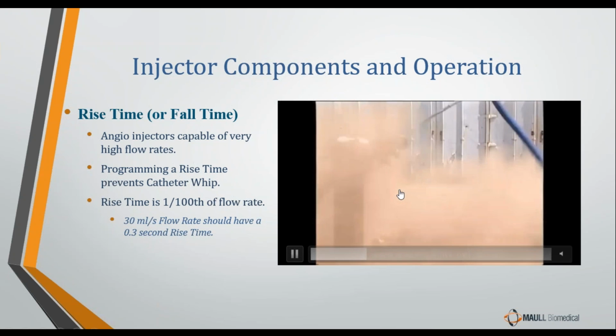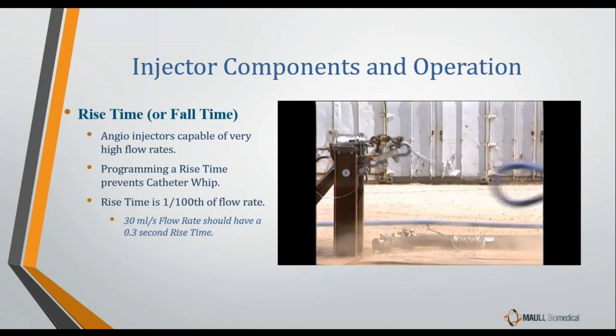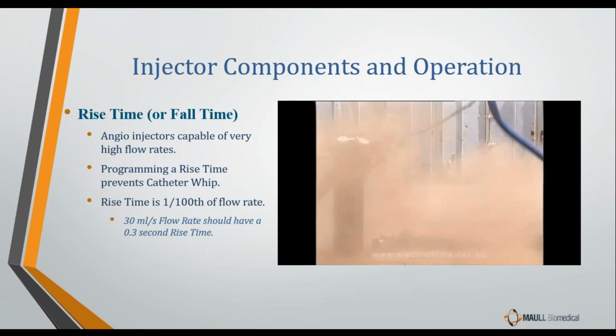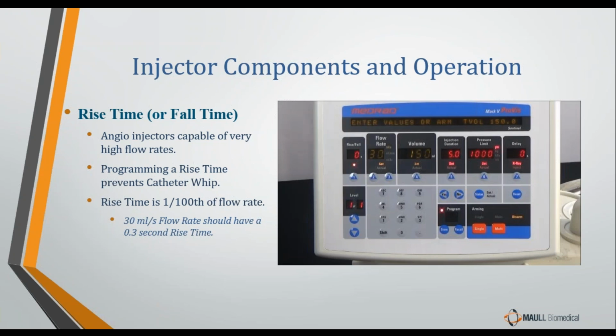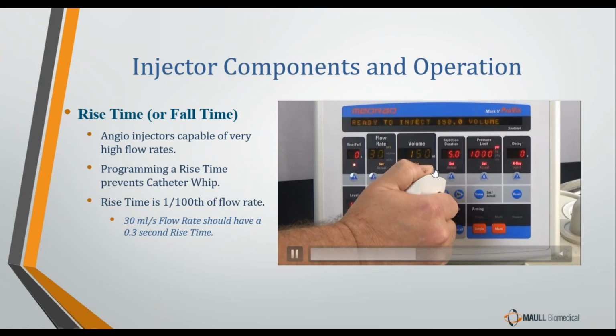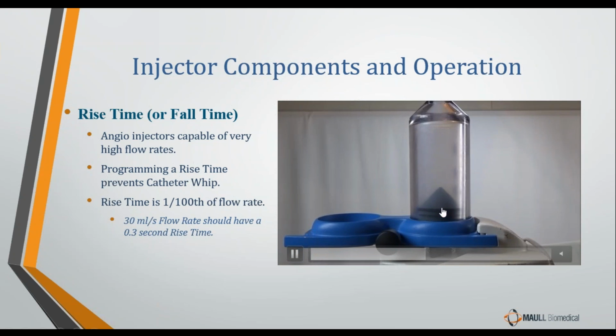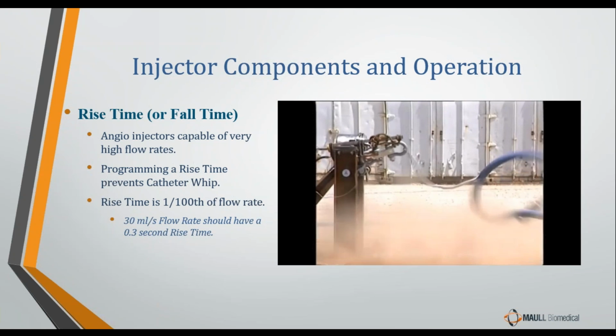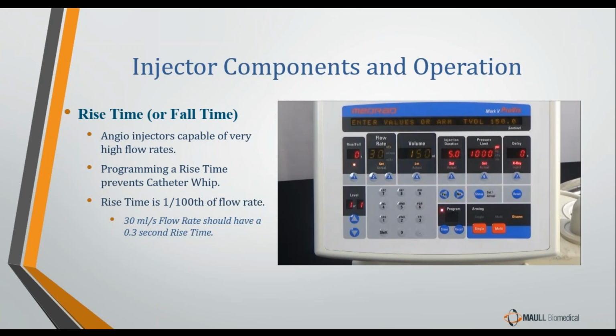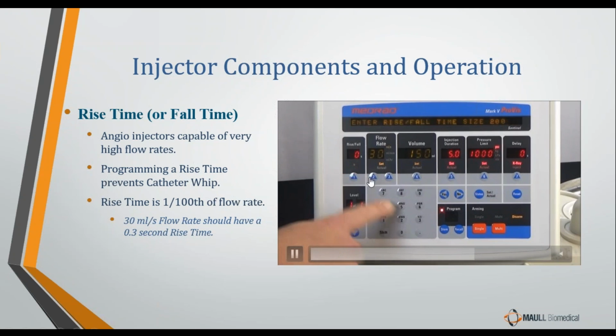So to prevent this, and actually this is just a demonstration of it. Here's an image of a tube going from nothing to instantaneous full blast. This is referred to as catheter whip. Okay. Now to keep that from happening, you see here we have a flow rate of 30 milliliters per second. We're going to perform the injection, and the syringe instantly goes to full speed. Now that can cause catheter whip. Now to prevent that from happening, what we can do is program something called a rise time. Now if you look right here, we're going to program a 0.3 second rise time.